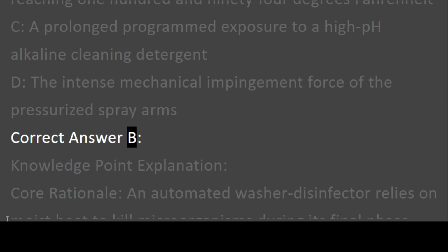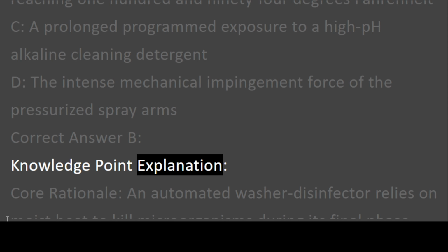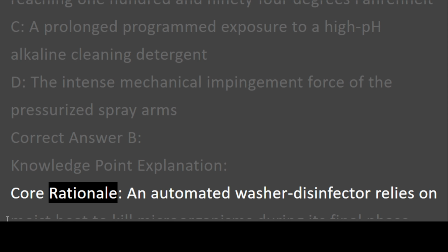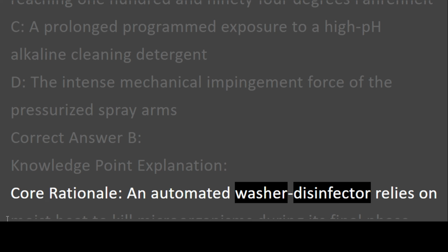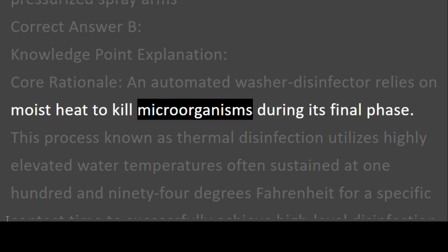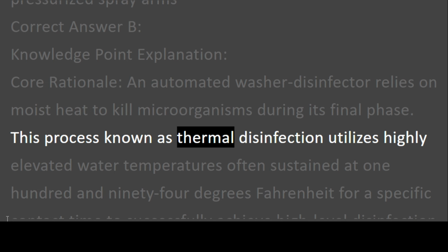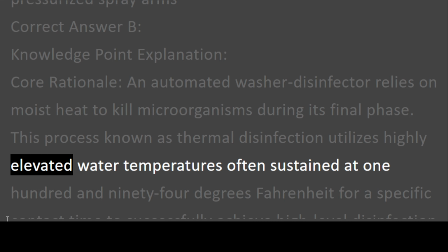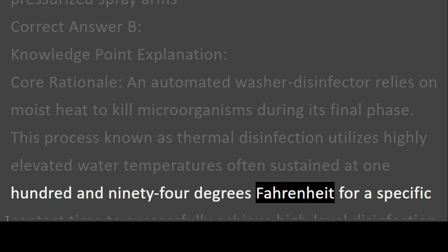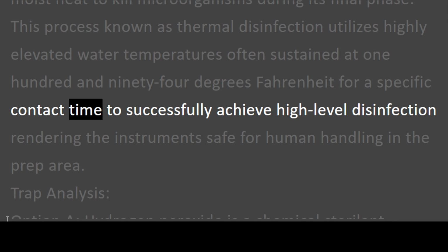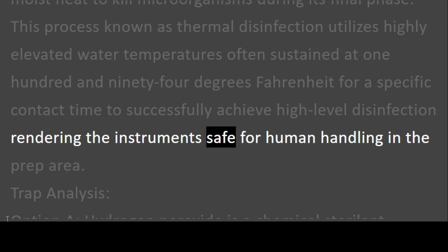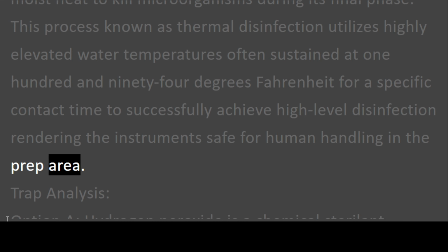Correct answer B. Knowledge point explanation. Core rationale. An automated washer disinfector relies on moist heat to kill microorganisms during its final phase. This process, known as thermal disinfection, utilizes highly elevated water temperatures, often sustained at 194 degrees Fahrenheit, for a specific contact time to successfully achieve high-level disinfection, rendering the instruments safe for human handling in the prep area.